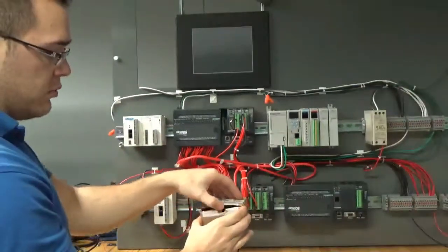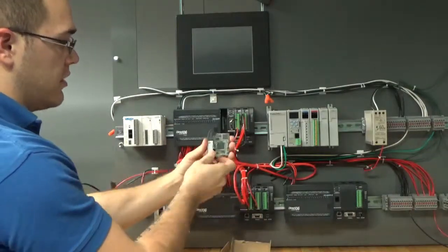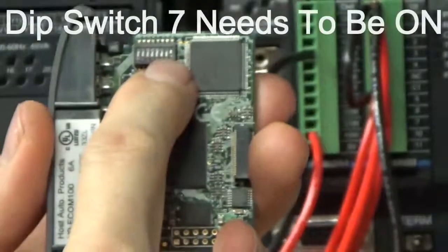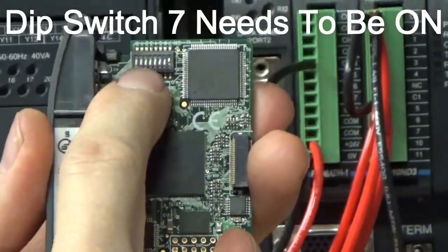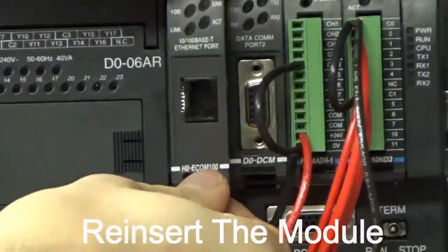Once you have a replacement, we're going to remove it from the box. Next, we're going to verify that DIP switch 7 is on and the rest of the DIP switches are off. Next, we're going to push it into the PLC nice and straight.